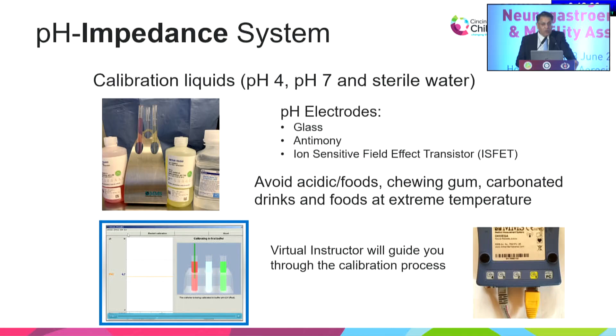You have to calibrate your catheter extremely carefully. There are calibration liquids with a pH of 4, 7, and sterile water. There's a whole system of virtual instructors online that will guide you through the calibration process. And you have to make sure that you ask the patient to avoid acidic foods, chewing gum, carbonated drinks, and foods at extreme temperature while doing the study, because it can affect the study.